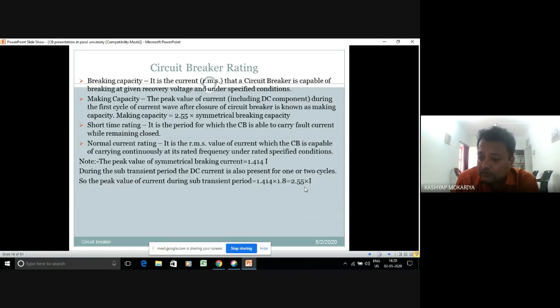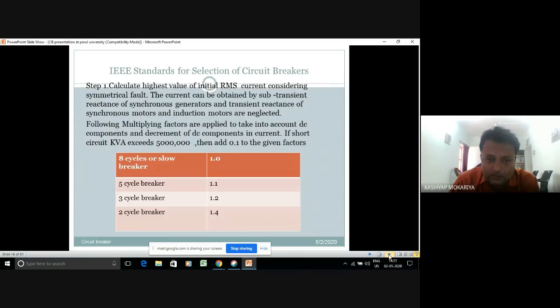Because once you design your breaker on the steady state conditions, it will be a false arrangement, because it will not take care of that high inrush, and there is every chance that the breaker contacts might get damaged. So this was related to some basic breaker concepts. Say, I have shown one example here: IEEE standards for selection of breakers.